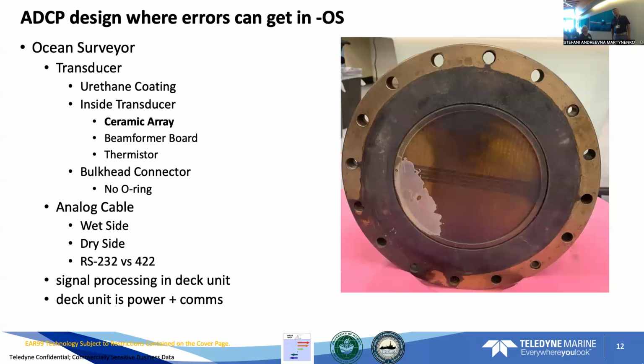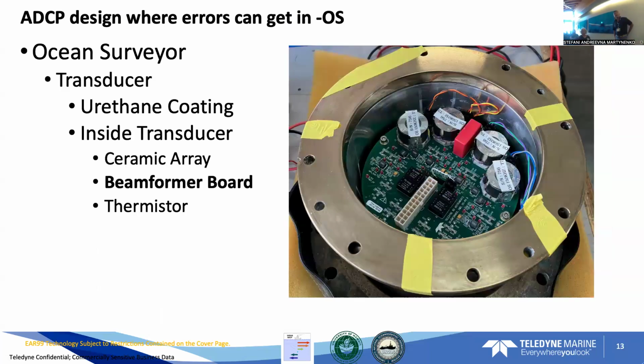And so you can see it's burnt there. The beamformer board, this is the beamformer inside the transducer. And there's only one board in there. We made a change in 2016, and we don't have a lot of beamformer board failures anymore. So if you have a much older transducer, we'll keep an eye on that. But since 2016, we've had a lot less. They're very uncommon.